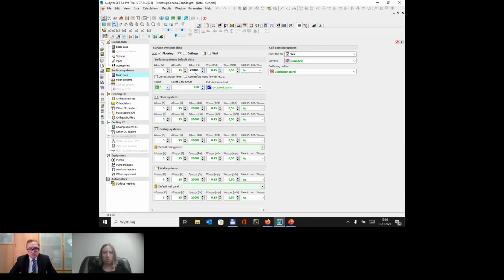Also, we can have the risk of noises. So generally, we reduce the temperature drop if we need to increase the power, but generally it's not recommended to go under 5. The program accepts even from 1, but I think 1 is rather low.